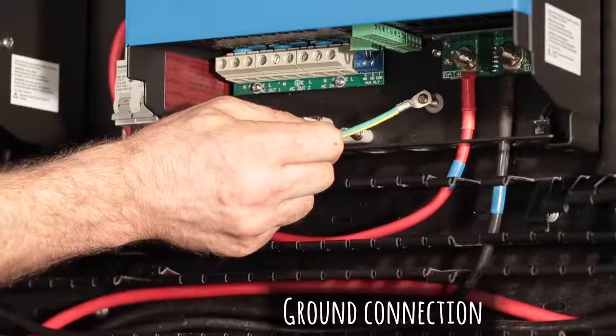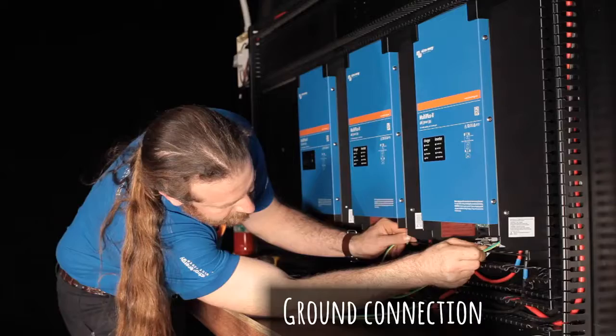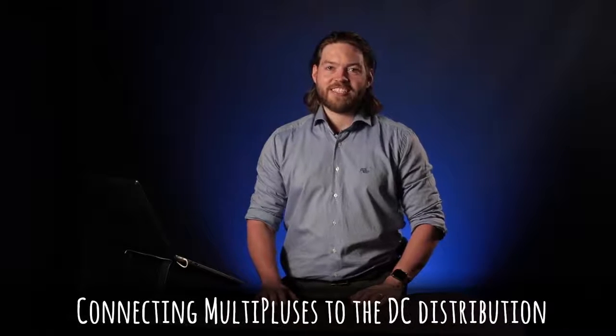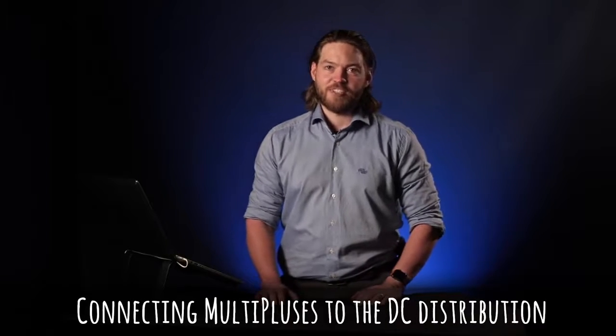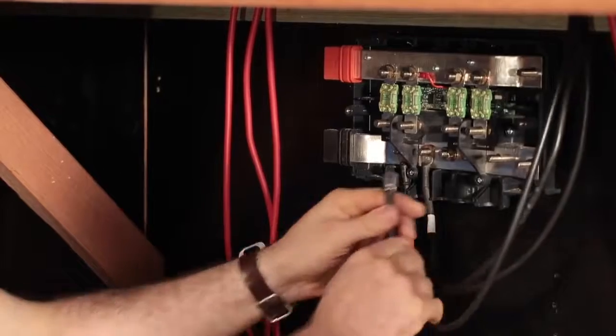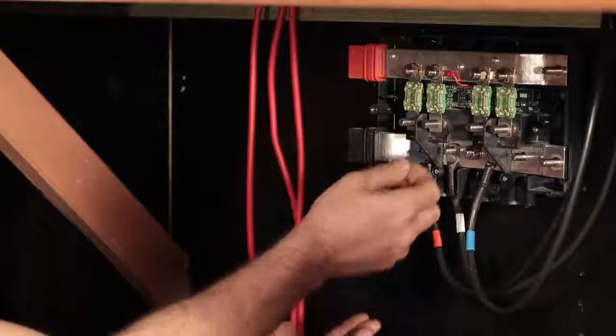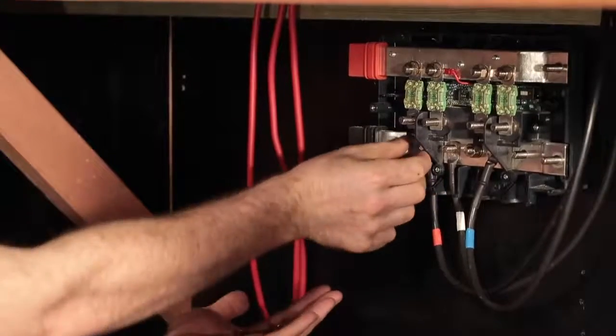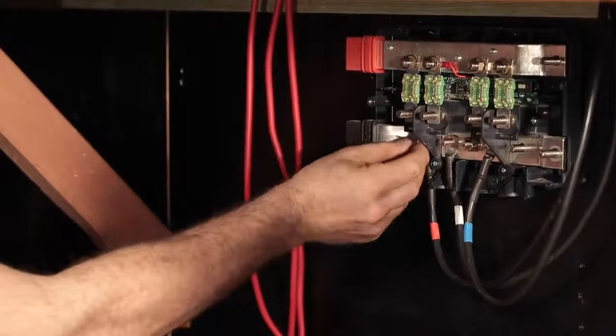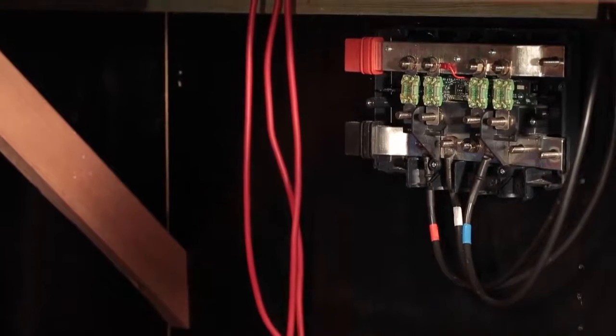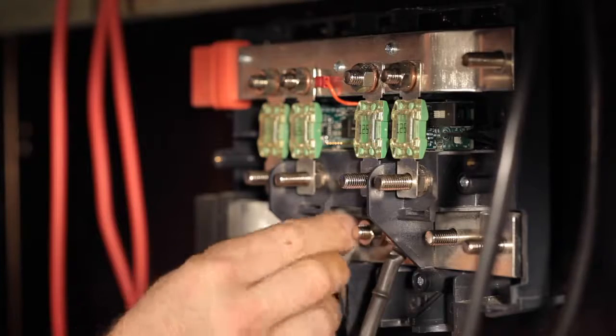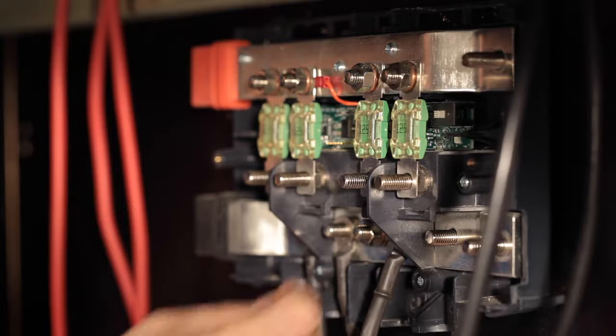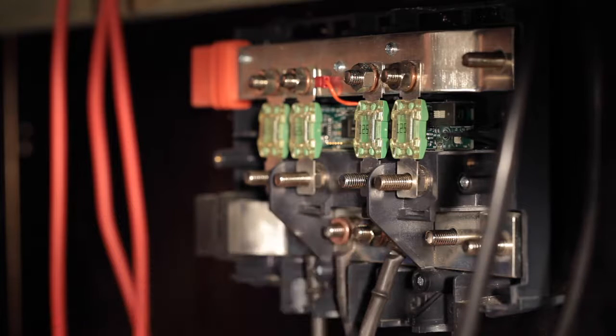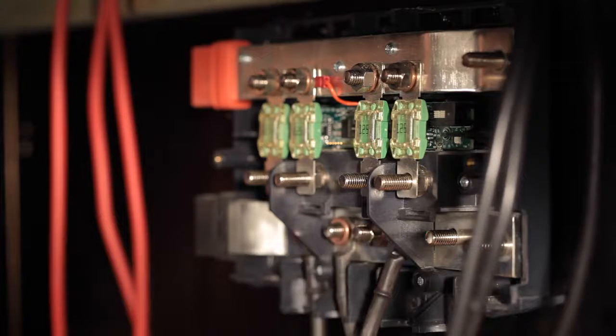If you've got a ground connection, this is where it's connected to the chassis of the unit. Ground connections vary according to your region, so please follow your local wiring rules. We can now connect our battery negative cables to our DC distribution. In this case, we're using a Victron distributor. If you remove the front cover and then the plastic plates over the negative DC bus bar, you can attach the lugs from the battery cables onto the bolts and then tighten them up with the nuts. As with the others, it's a flat washer, then a spring washer, and then the nut.